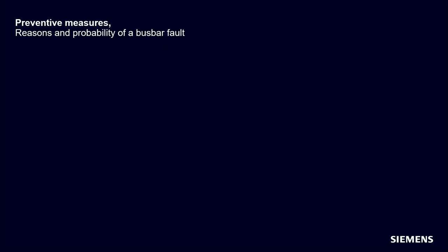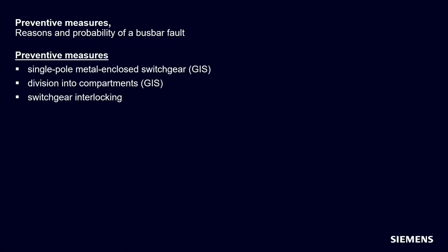Reasons and probability of a busbar fault. What are the typical preventive measures? Typical preventive measures are single-pole metal-enclosed switchgears, so-called GIS stations. And with GIS stations, we also have a division into separate compartments. This greatly reduces the probability of a short circuit in our busbar protection. And of course, state of the art, you typically also have switchgear interlocking available in each substation.